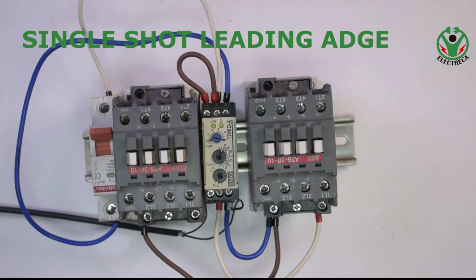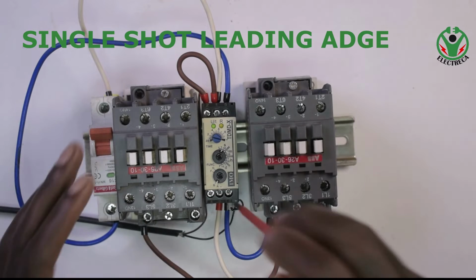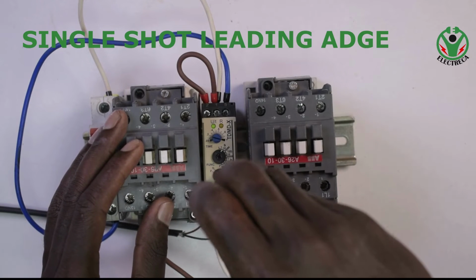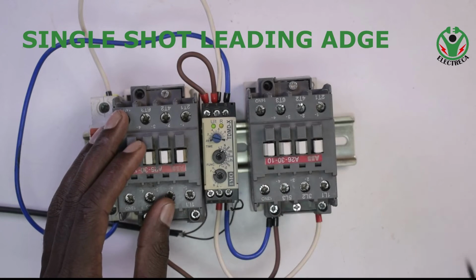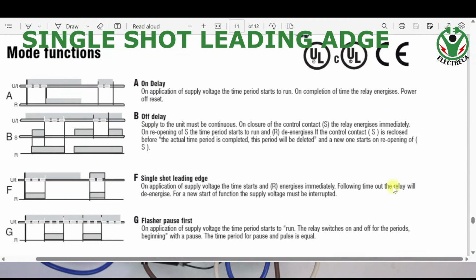Now, let us look at F, which is a single shot leading edge. You put in F like that, and then you switch on. This says that on application of supply voltage, the timer starts to run immediately. So the relay will energize immediately. Following the timeout, the relay will de-energize. For a new start, you will have to interrupt the power supply.